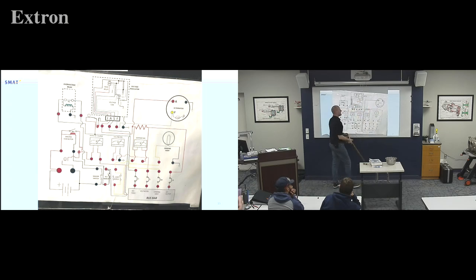So A is our output on our alternator, which is connected both to the bus and to the regulator, just so it knows what voltage it's getting. F is the field voltage, to say hey, I want power. S, on this drawing, you say, start making power, closes that one. And then that leaves I. I is that indicator light.